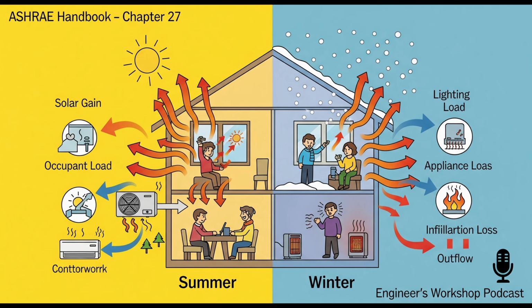That hurts efficiency. But the bigger issue was leaks, right? Oh, yeah. The handbook really flags duct leakage as a massive problem. I feel like I've heard some scary numbers about that. The sources quote figures like 10%, even up to 35% or more of the air leaking out of ducts in some houses. 35%. Wow. So all that careful calculation of heating or cooling needed for a room. Right. If a third of your expensive conditioned air is just leaking out into the attic or walls, it totally undermines the whole system design. Supply leaks mean air doesn't get where it needs to go. Return leaks mean you're sucking in dusty, hot, or humid air from places you shouldn't be, making the system work way harder. That's huge. A massive potential waste. It's a major gap between design calculations and real-world performance.